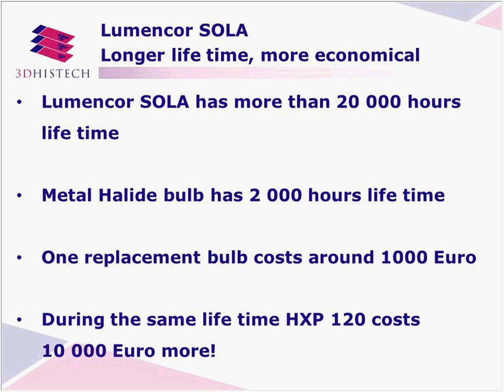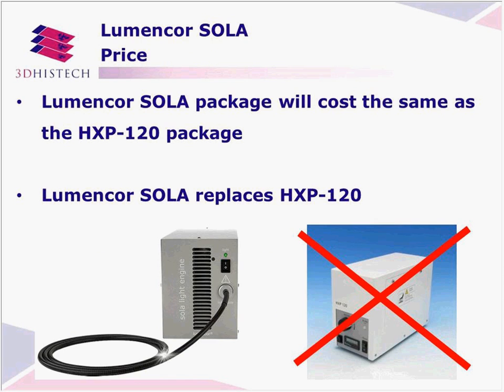Also, in a typical usage pattern, the metal halide lamp has to be turned on 15 or 30 minutes to really warm up and work properly. For the SOLA, 1 second is sufficient to turn on. So the hours in which the system is used are fewer compared to the HXP 120. The price will be the same as the HXP 120 package. The package includes the light source itself, the power supply, the liquid light guide, and the coupler to the microscope.